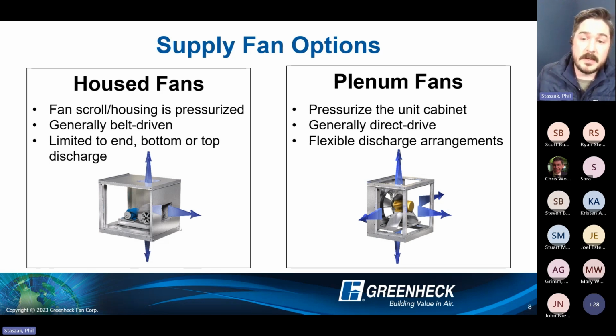And in some cases, say we make a mistake, the unit is ordered as end discharge, gets out into the field, and you say, you know what? It would be really nice if we could actually turn this unit sideways and come out the side. Most of those panels are typically interchangeable, so you can just swap the panels out. Opens up your discharge arrangements and your flexibility in the field.